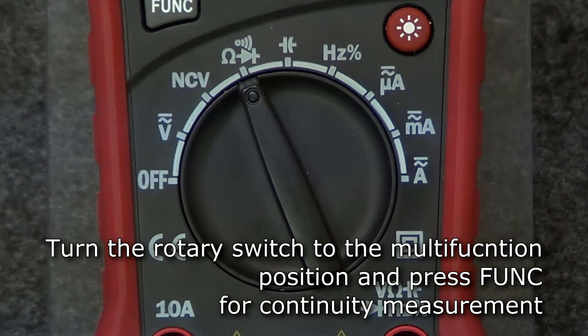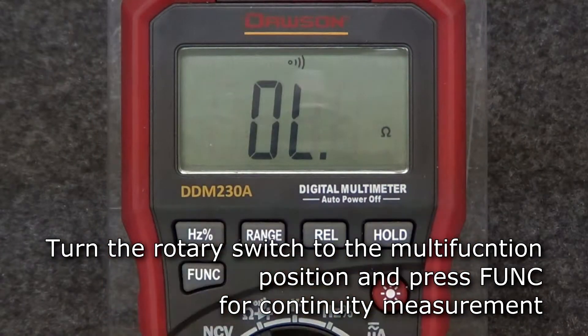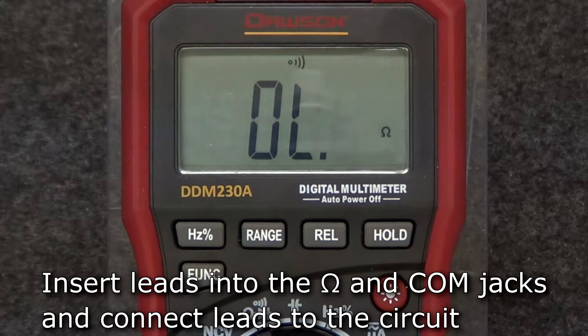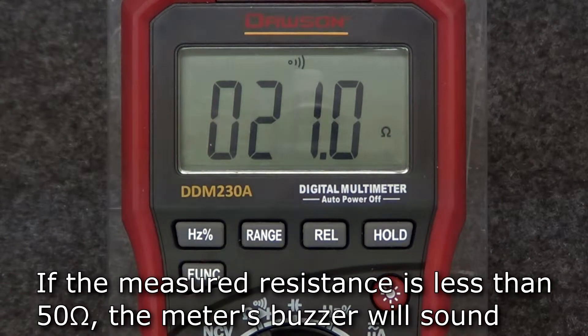To measure continuity, turn the rotary switch to the multifunction position. Press the function button to switch to continuity mode. Insert the test leads into the ohms and COM jacks and connect the leads to the circuit under test. If the measured resistance is less than 50 ohms, the meter's buzzer will sound.